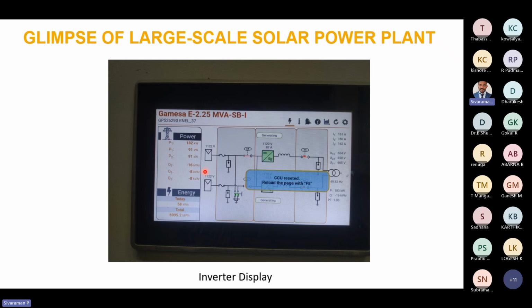of reactive power from the grid. So whenever you are seeing a solar power plant or solar inverter, direction is important, because a solar inverter can operate in four quadrant operation: exporting the real power and exporting the reactive power, exporting the real power and importing the reactive power, and exporting the reactive power and importing the real power.